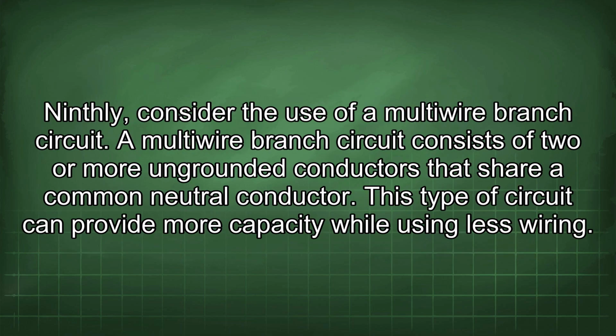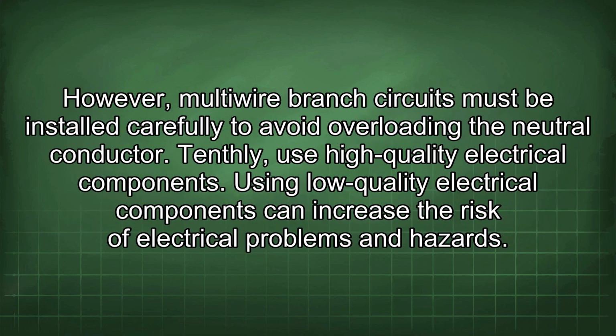Ninthly, consider the use of a multi-wire branch circuit. A multi-wire branch circuit consists of two or more ungrounded conductors that share a common neutral conductor. This type of circuit can provide more capacity while using less wiring. However, multi-wire branch circuits must be installed carefully to avoid overloading the neutral conductor.